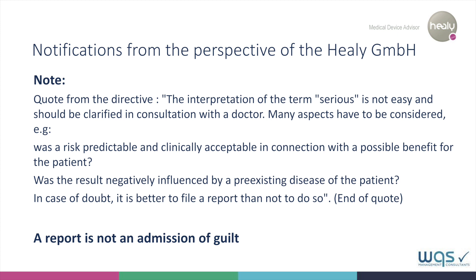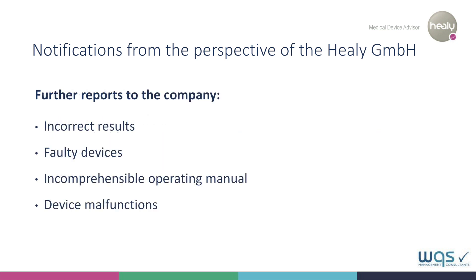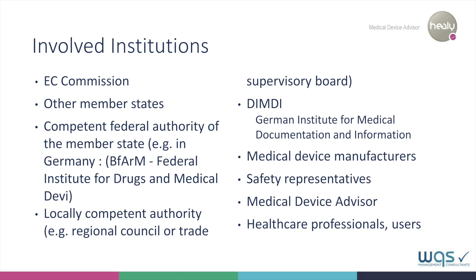Note: a report is not an admission of guilt. In the event of an incident, its causes must be clarified — was it or could it have been caused by the product, its application, or the information associated with the product? Other issues that we as MDAs also need to report are incorrect results and faulty devices, and an incomprehensible operating manual. On this slide, we see the institutions and groups of people involved in the process of reporting.